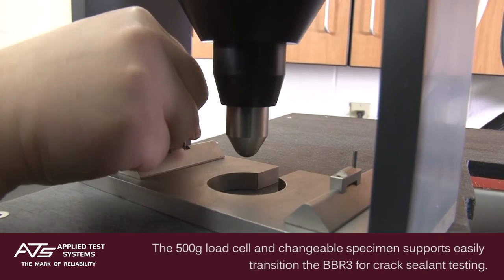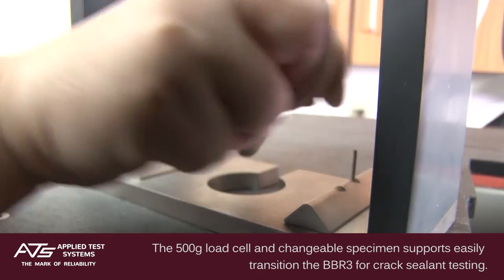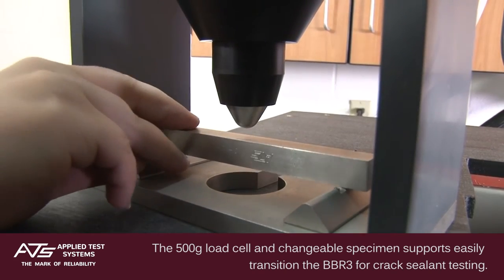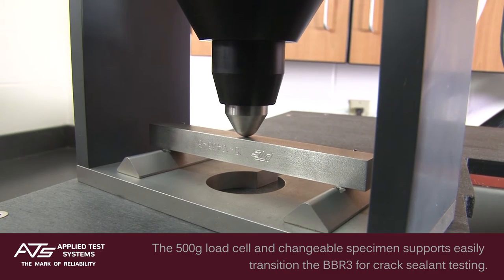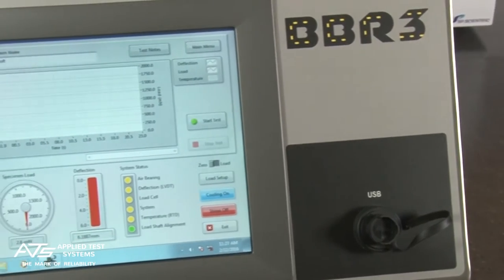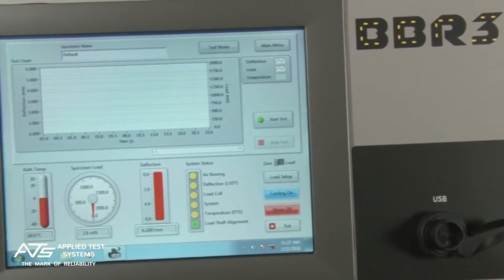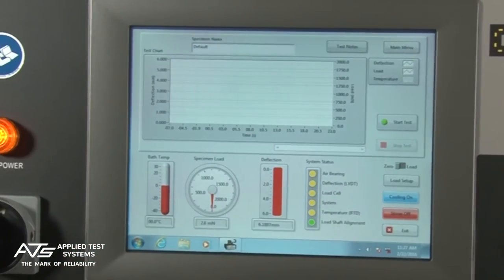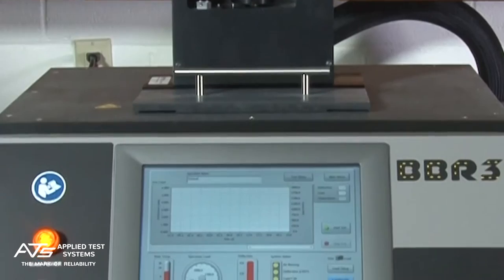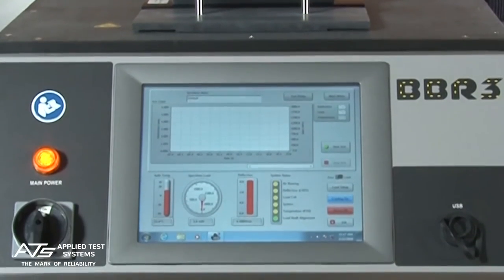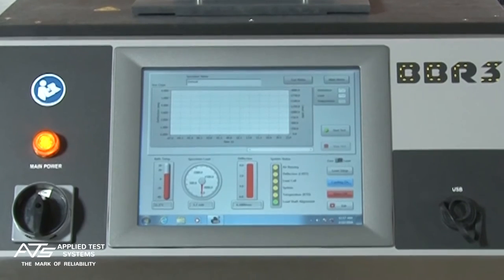The 500 gram load cell and changeable specimen supports easily transition the BBR3 for crack sealant testing. The BBR3's built-in computer replaces the external computer used with previous BBR models and features a 12-inch touchscreen display.